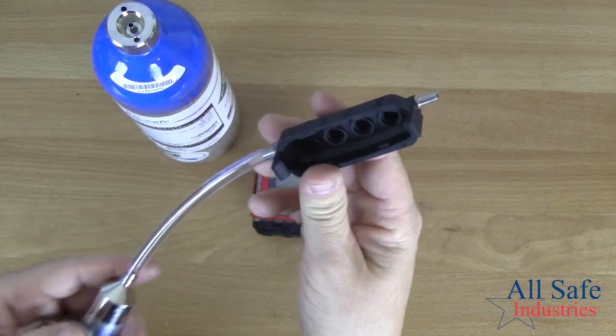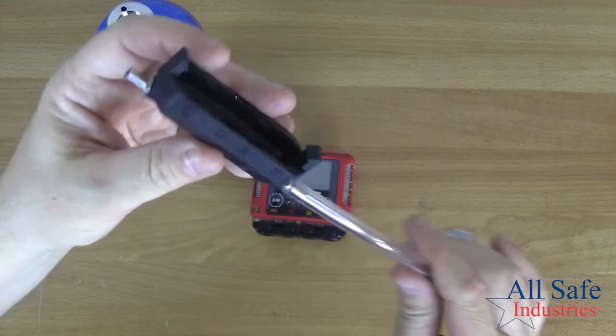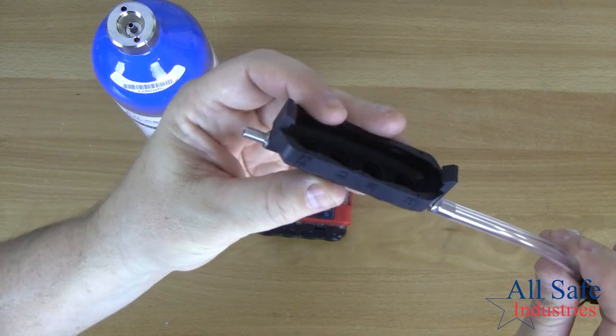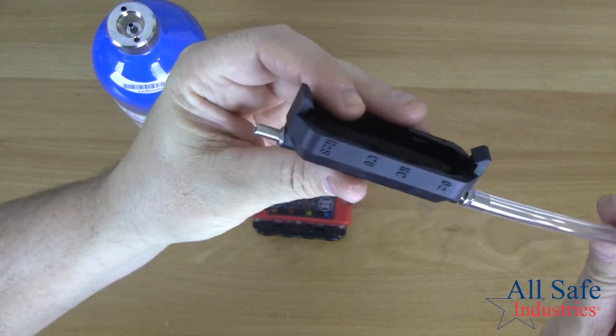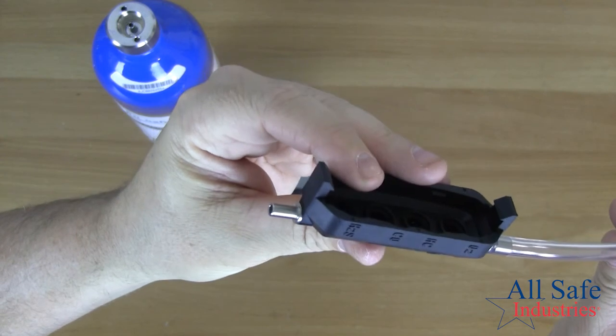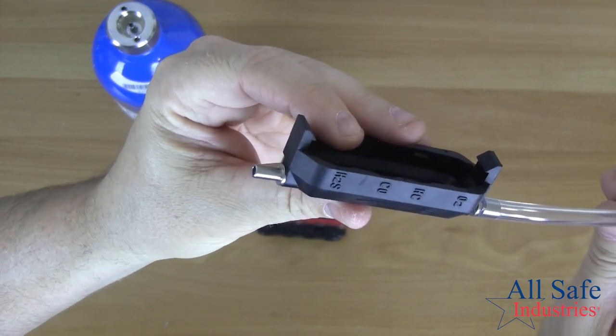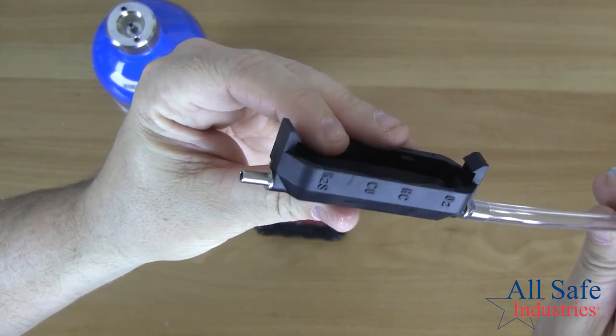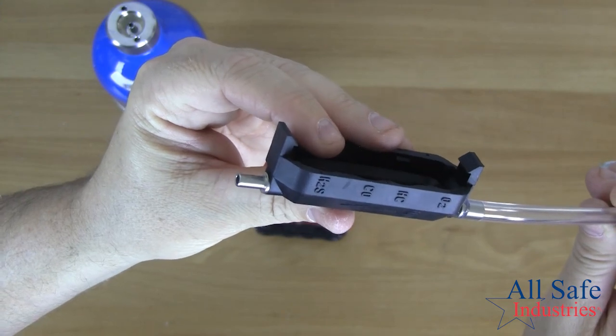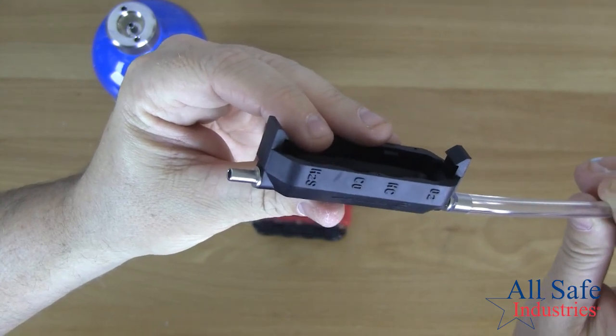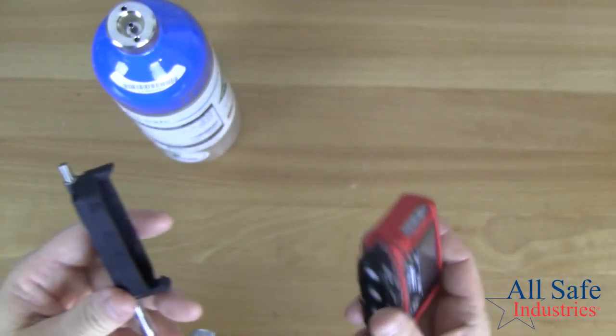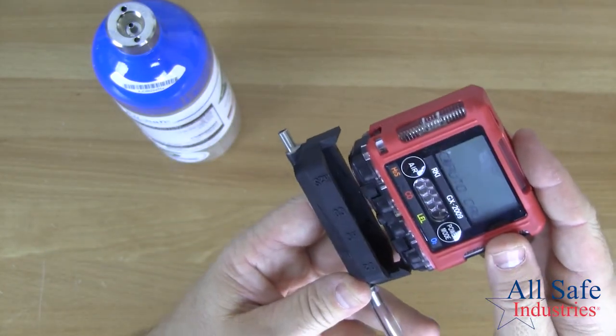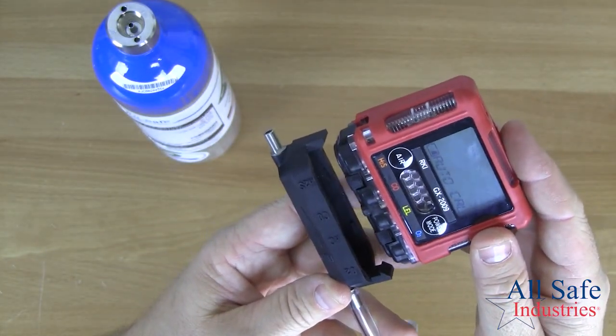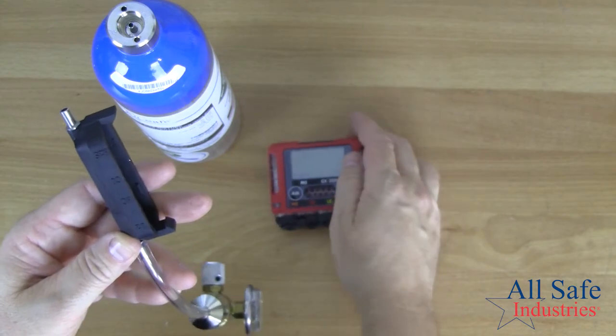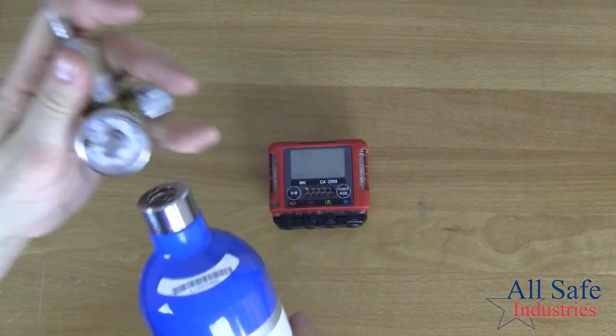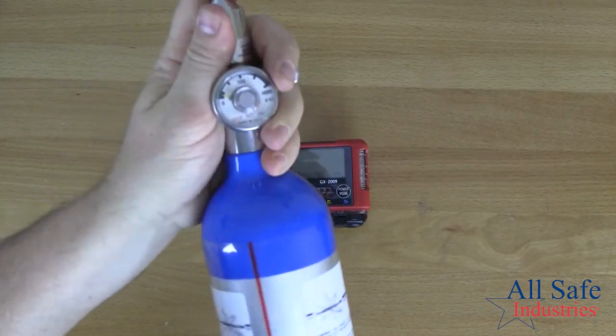The other thing I need is my calibration cup. The calibration cup is what feeds the gases to the sensors, and you can see it's a black molded part, but with the reflection of the light you can see there's sensor labels on the side of the cal cup, and you're going to want to match those up with the sensor labels on the side of the instrument. So you'll put this in here like this. But first, let's take our regulator and engage that onto the cylinder of gas.